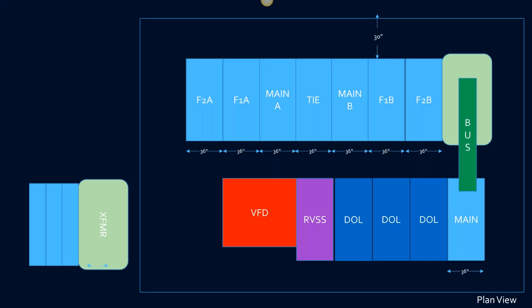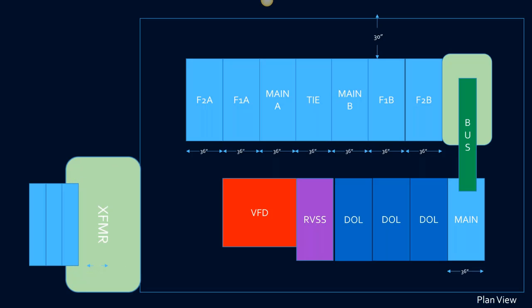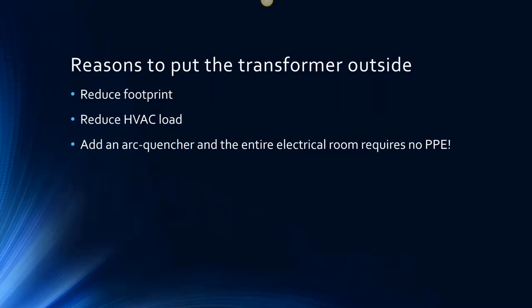that's a good thing, and we'll talk more about that in a second when Mike takes over. But so we reduced the footprint of the load. That's one reason to put a transformer outside. We reduce the HVAC load, and you know, add an arc quencher to the secondary of that transformer, which is what Mike has made his living doing, putting arc quenchers in the secondary of liquid-filled or cast coil transformers. Put an arc quencher in the secondary of that transformer, and now your electrical room requires no PPE.